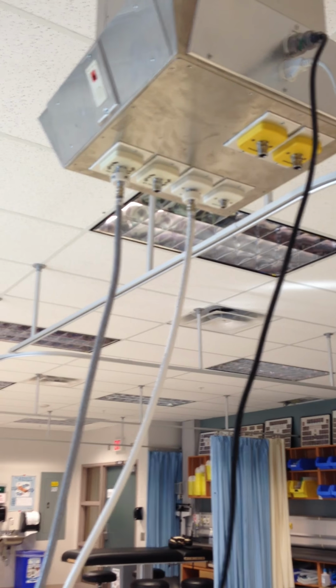If we come around to the back here, you'll find your power switch. Hook that up. You'll hear an audible alarm. It's going to do a bit of a short self-test, or machine test. We're doing the self-test. I've already got this plugged into 50 psi O2 air and to AC power.